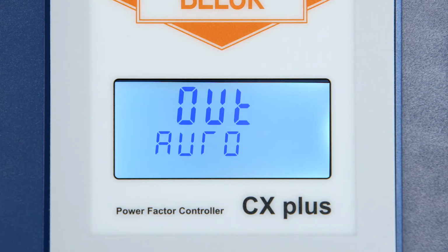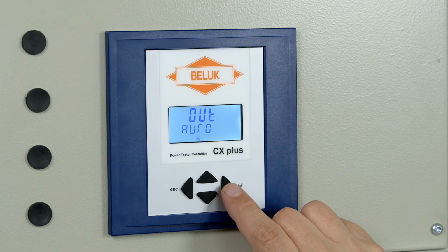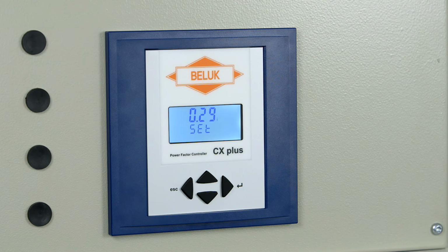Now the types of each output of the controller are set. These can be set Fix On, Fix Off, or to Automatic. Once again, commissioning is completed when the Power Factor control is switched on, PFC on. The CXplus shows the message First Setup OK in the display and the automatic control can begin.